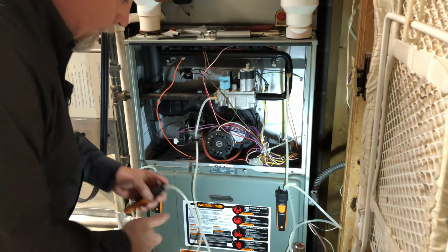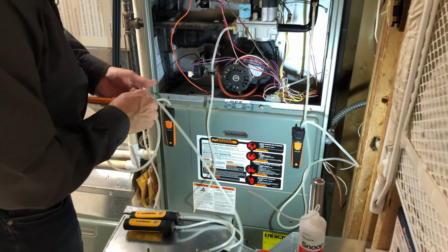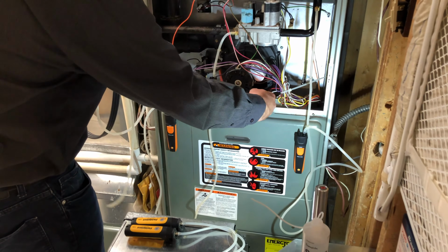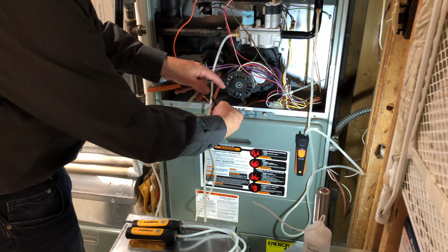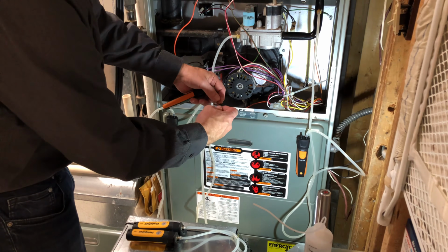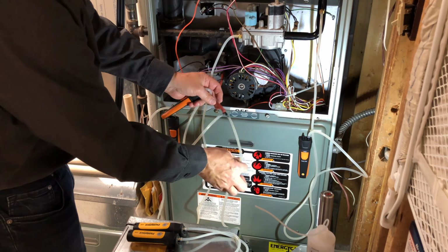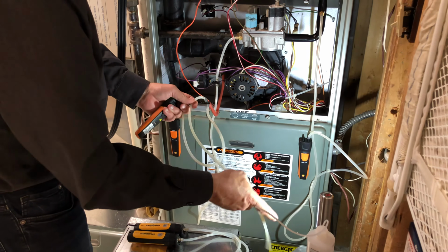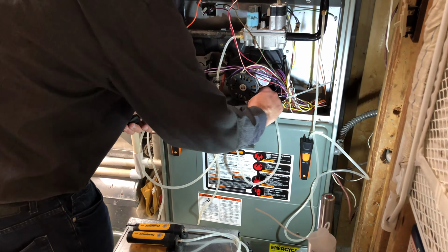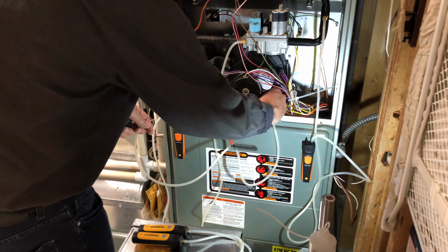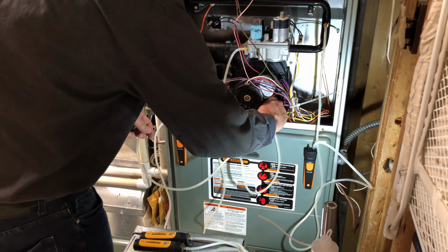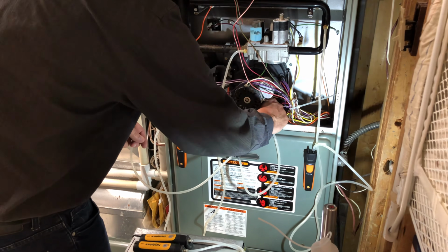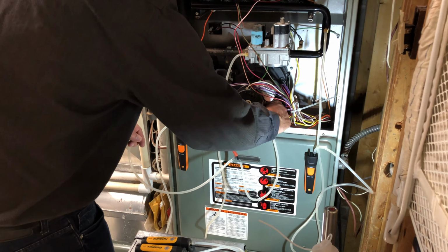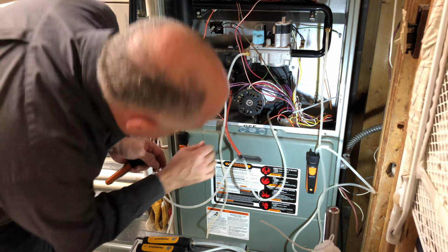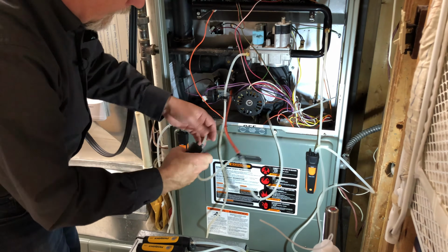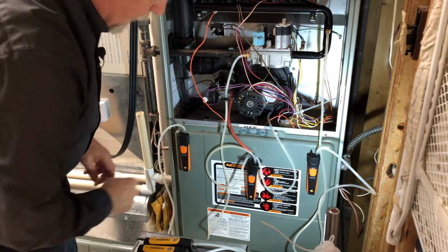Then I've got my induced draft pressure here. What I'm doing here is just testing the induced draft pressure that the inducer will pull. So I'm pulling this off, slipping this tube over this fitting here so I have a nice seal. And then I'm going to slip this tube back onto the port of the induced draft motor. What this is going to do is allow me to measure the pressure that's developed by the induced draft motor. So you can see that's hooked up down here. And I've got my three manometers hooked up now.